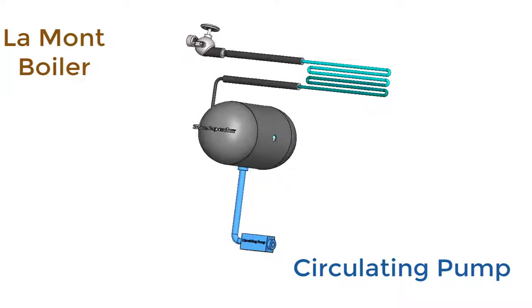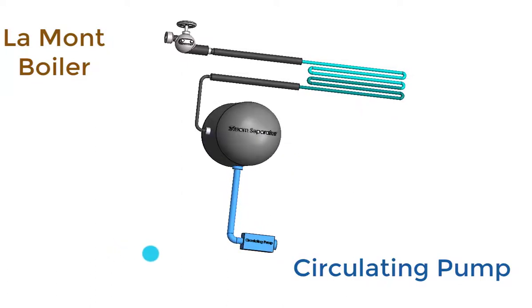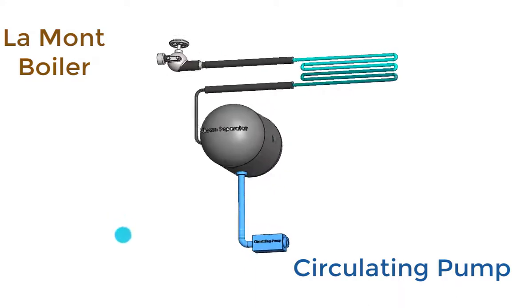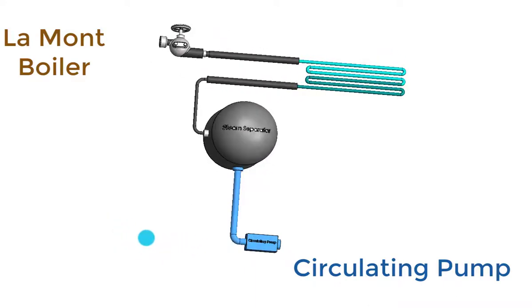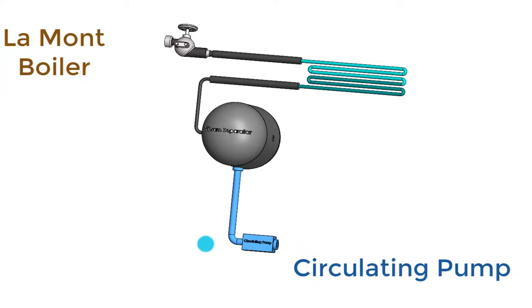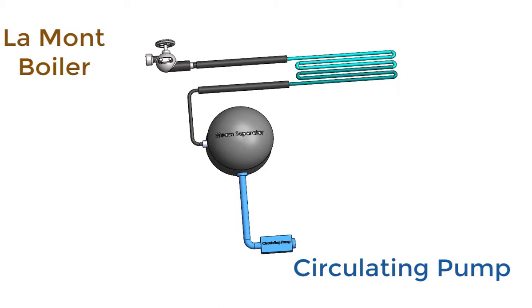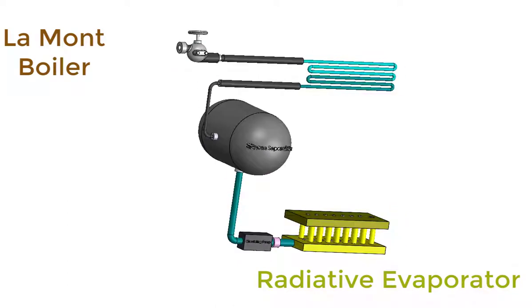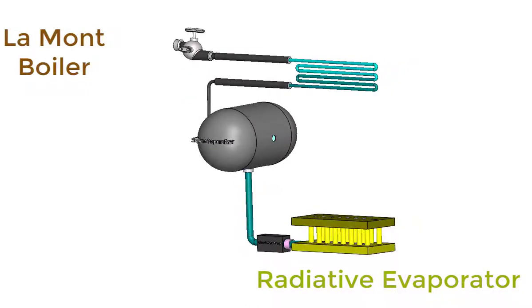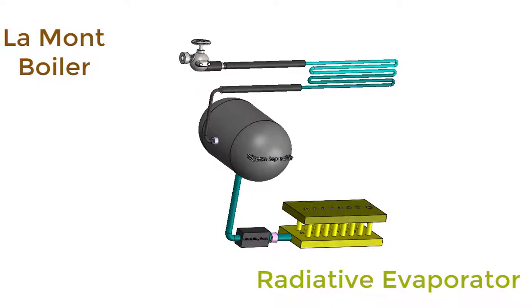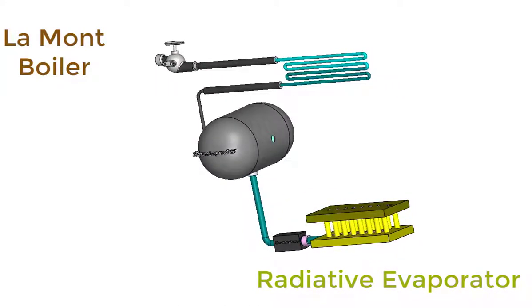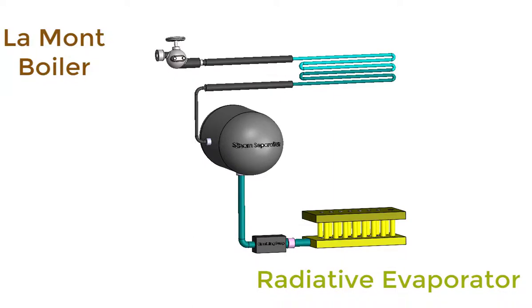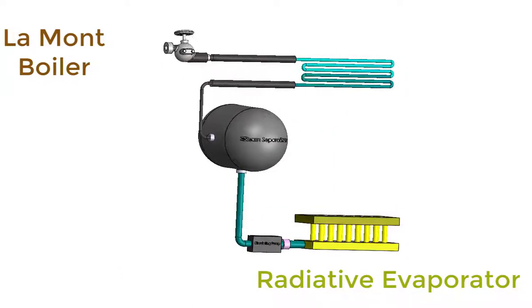Water from the steam separating drum is drawn by the circulating pump and it circulates water through evaporator tubes under pressure, because the Lamont boiler is a forced circulation boiler and for that it needs a circulating pump. Now the radiant evaporator — water from the drum enters the radiant evaporator through the circulating pump. The water is heated by radiant heat from the combustion chamber. Generally, the radiant tubes are attached to the walls of the refractory structure near the furnace.